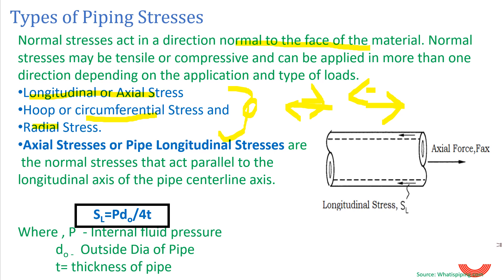Longitudinal or axial stress acts parallel to the longitudinal axis — the pipe centerline axis. It is given by the formula: S_L = P·D₀ / (4t), where P is the internal pressure of the fluid, D₀ is the outside diameter of the pipe, and t is the thickness of the pipe. This stress acts and tries to deform the pipe from its actual support position, and the pipe supports resist this movement.